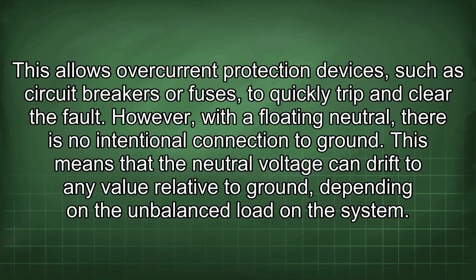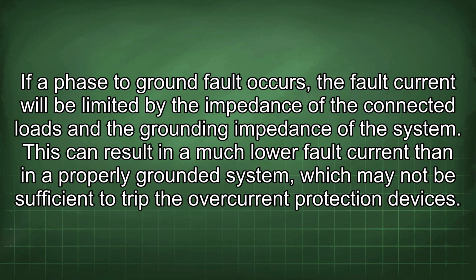However, with a floating neutral, there is no intentional connection to ground. This means that the neutral voltage can drift to any value relative to ground, depending on the unbalanced load in the system. If a phase to ground fault occurs, the fault current will be limited by the impedance of the connected loads and the grounding impedance of the system. This can result in a much lower fault current than in a properly grounded system, which may not be sufficient to trip the overcurrent protection devices.